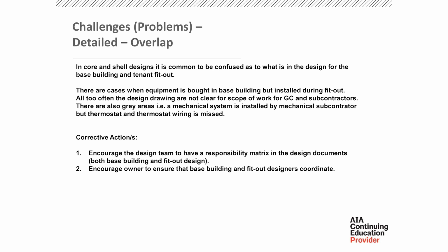In commercial design, it is common to be confused as to what is for the base building and what is for the fit out. There are cases when equipment is bought on the base building but not installed until the fit out. All too often, design teams are not clear on scope of work with the GC and subcontractors. There's also a gray area, i.e. a mechanical system is installed by a mechanical contractor, but thermostat wiring is missed. Encourage the design team to have the responsibility matrix in the design documents, both base building and fit out design documents, and encourage the owner to ensure that the base building and fit out designers coordinate.